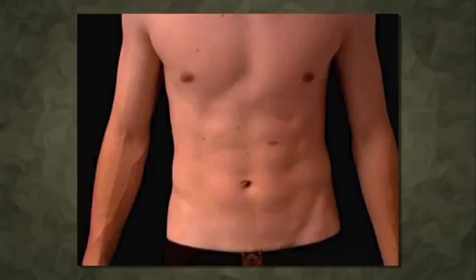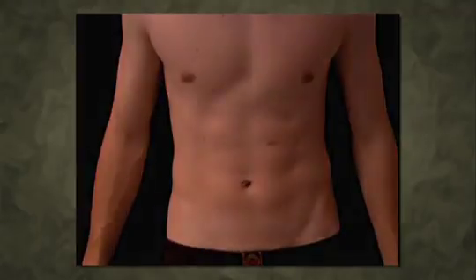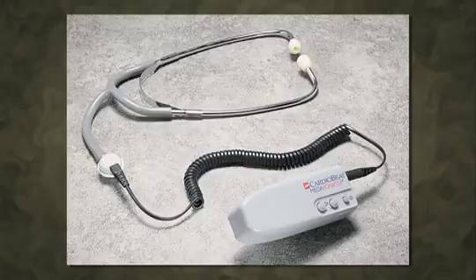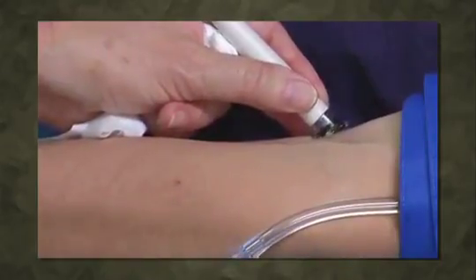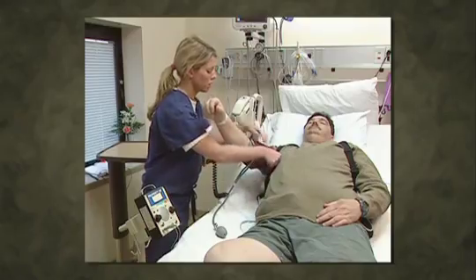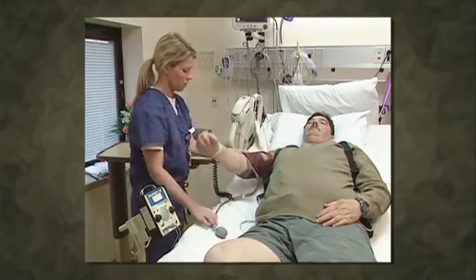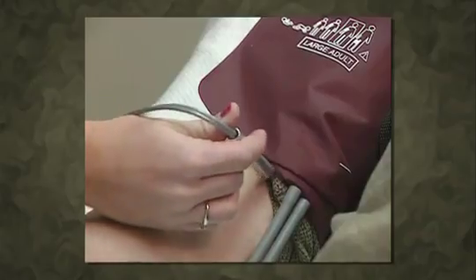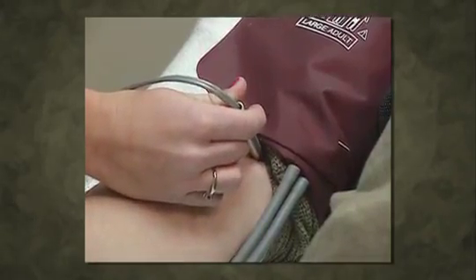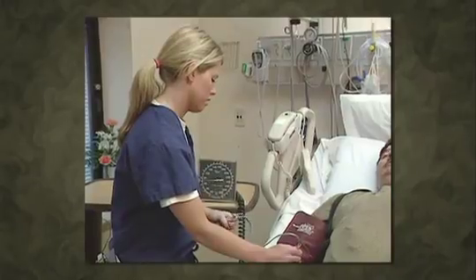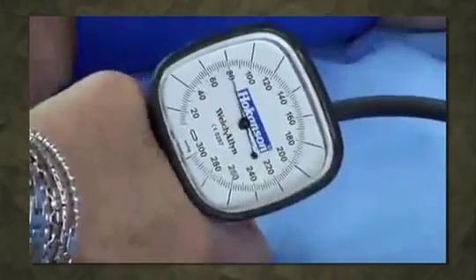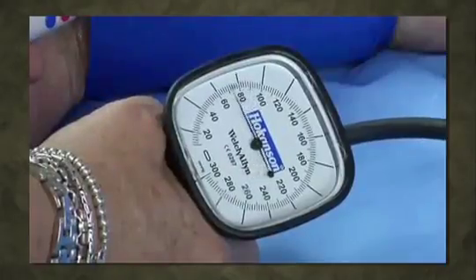After inspecting the system controller, listen over the left side of the abdomen with the stethoscope for a humming sound. If the pump is functioning, you should be able to hear this sound in both the left upper and left lower quadrants. Also, check with the patient to see if they have a Doppler stethoscope, as this will be the only way for you to assess their blood pressure. When using a Doppler stethoscope, you will only be able to obtain a systolic blood pressure. Prior to cuff inflation, listen to the brachial artery in order to hear a whoosh. Then pump up the cuff until the sound goes away. You should only need to go as high as 120 millimeters of mercury. As the cuff deflates, the first sound you hear will be the patient's blood pressure.